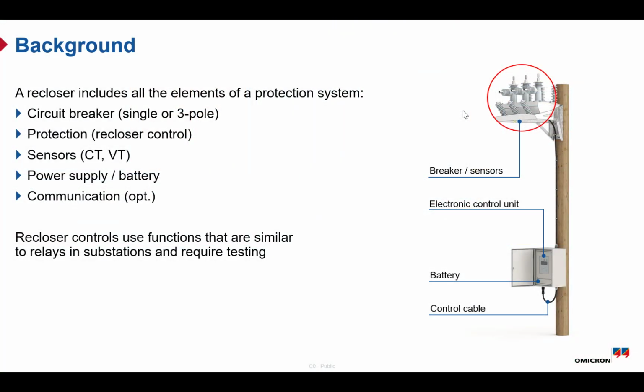Before we go deeper into testing, let's quickly understand what a recloser consists of. A recloser is not just a switching device, it actually includes all the key elements of a protection system, similar to what we see in a substation, but all combined into one compact unit. First, we have the circuit breaker, which can be single phase or three phase, and this is what interrupts the fault current. Then we have the recloser control.